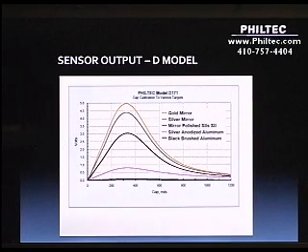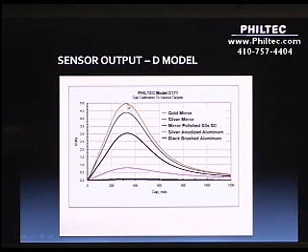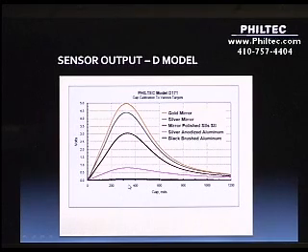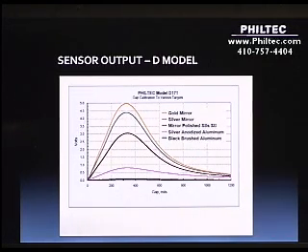If we look at the output of the D model sensors, you can see when we scale the output so the gold mirror achieves full scale or 100% output, there's a very large variation in the output of the D model sensor. With the black target, there's nearly a 100% reduction in the amplitude of the output. So there's a very strong sensitivity to the reflectance of the target surfaces, and hence we refer to these models as D models or reflectance dependent sensors.